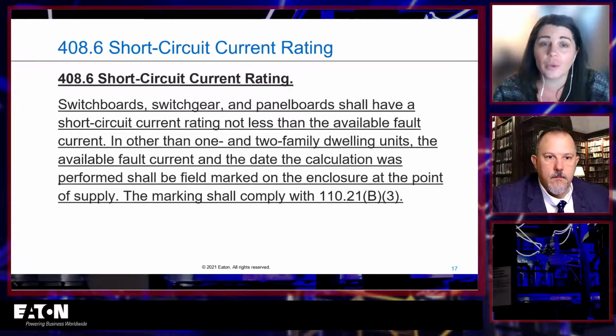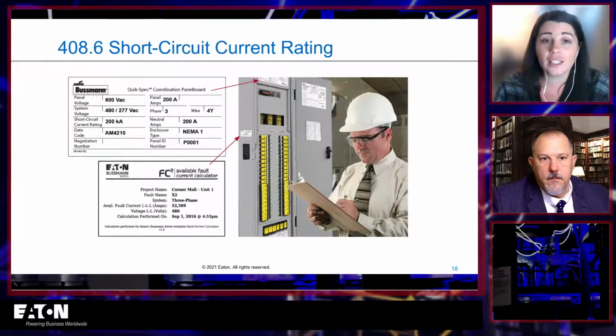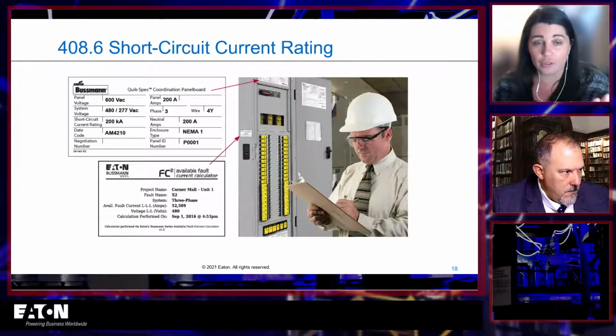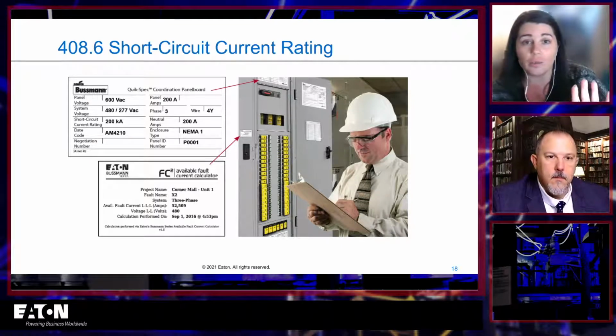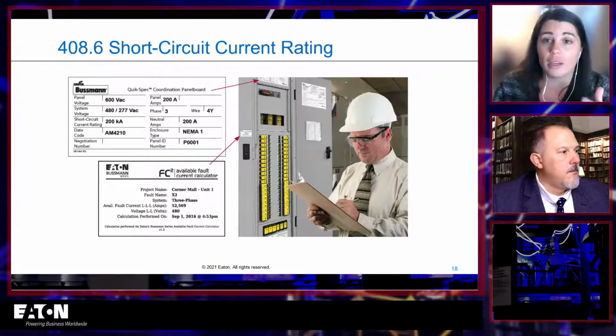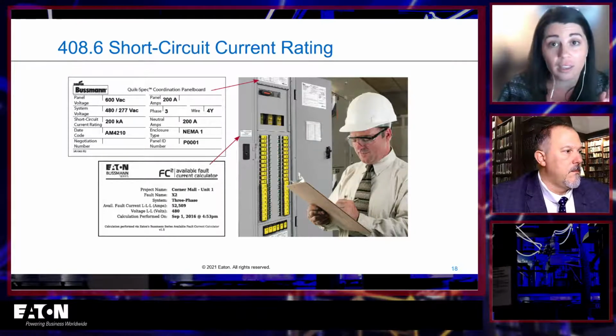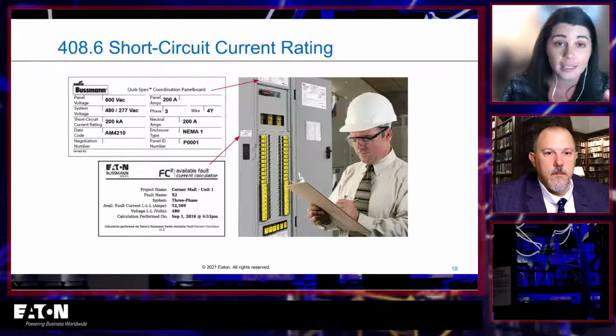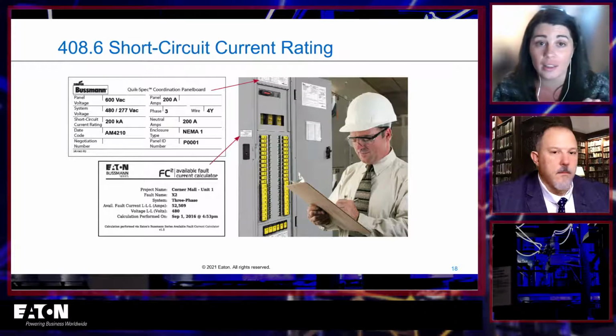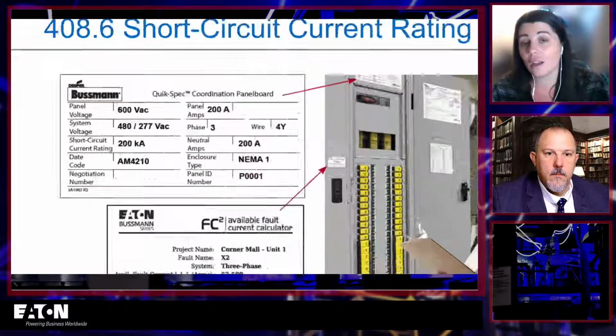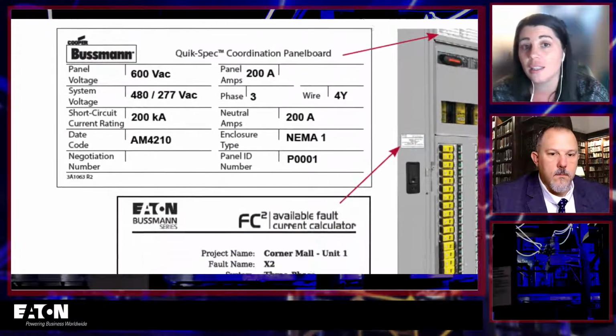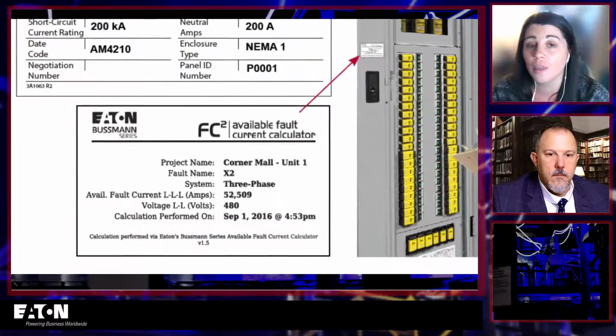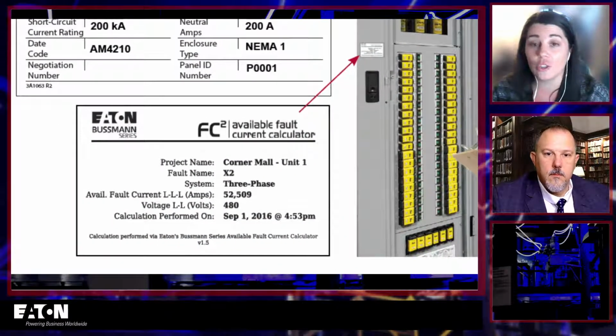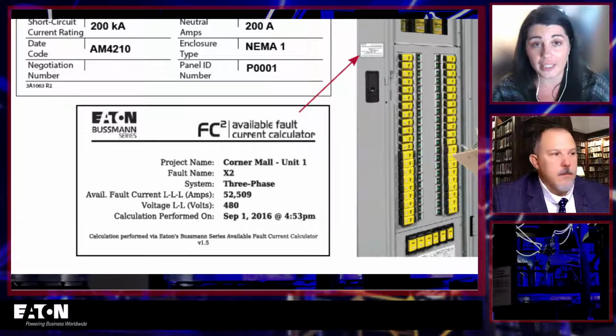You go to the next thing, I just want to highlight. So this is an example. This is sort of the easy version of a short circuit current rating and available fault current, right? This is a fusible panelboard. It is listed with a short circuit current rating on it. And then you have the label right below it showing you what the available fault current is, the date the calculation was performed, everything that should be on there per the NEC.